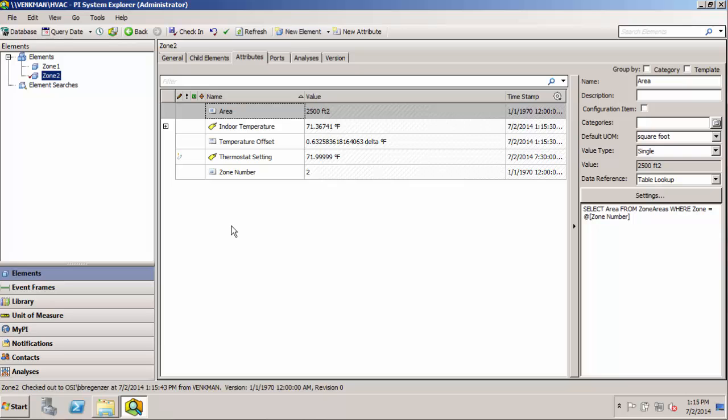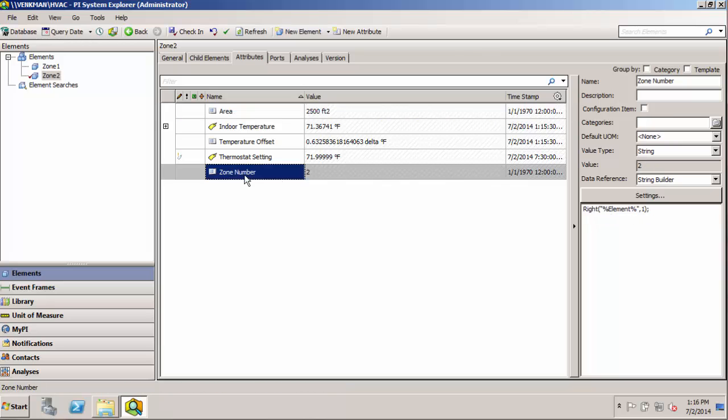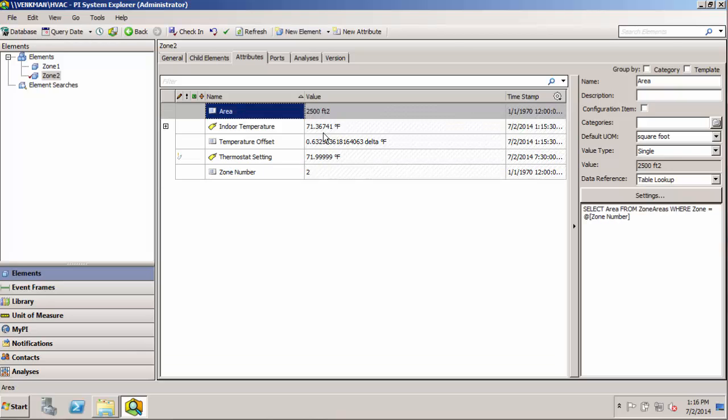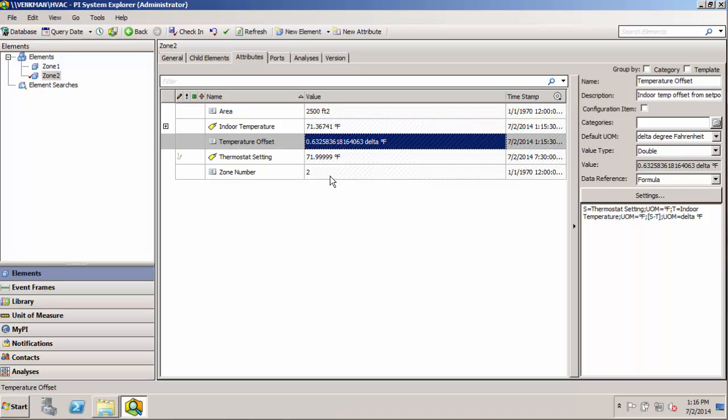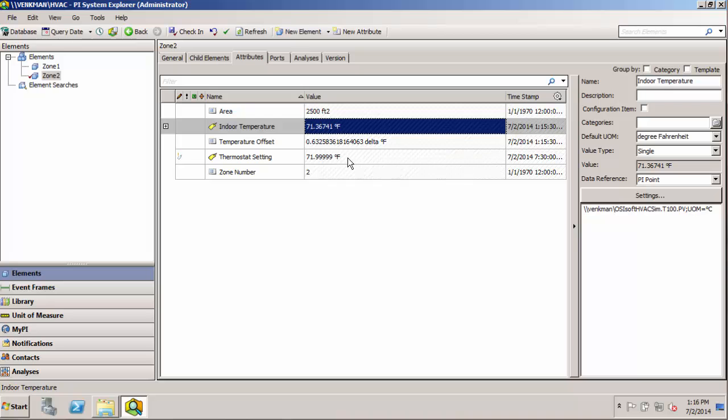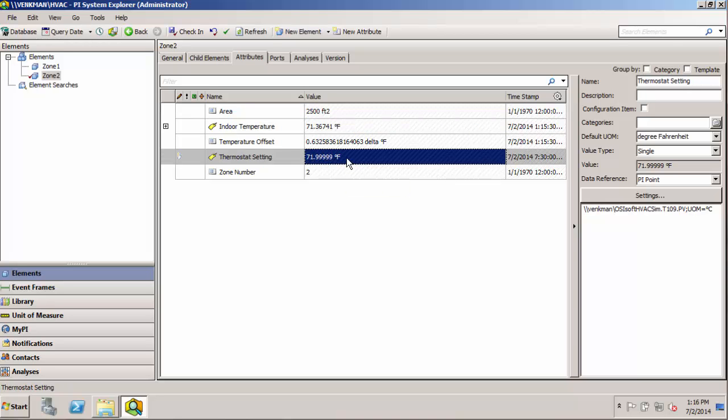And we can see because we did some smart stuff with our data references that this zone number based on the string builder data reference gets the two from the element name. And of course our table lookup takes that two and looks up a proper area for us. And we have our temperature offset formula reference already defined as the difference between these two tags. So really the only work left would be to go into these two pi point data references and go find the correct tag for zone two.